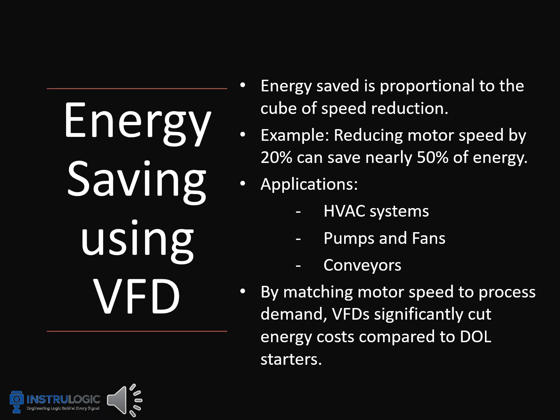One of the biggest advantages of using a VFD is energy saving. Energy saved is proportional to the cube of speed reduction, meaning even a small reduction in motor speed can result in huge energy savings. For example, reducing motor speed by just 20% can save nearly 50% of energy. VFDs are widely used in HVAC systems for controlling fans and blowers, pumps and fans in industrial processes, and conveyors for material handling. By matching motor speed to the actual process demand, VFDs significantly cut energy costs compared to DOL starters, which always run at full speed.